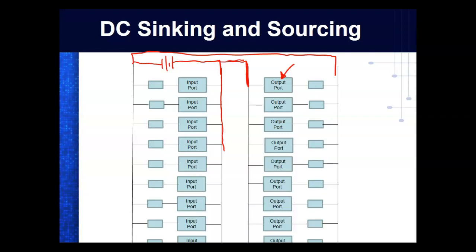So this is technically the way it's wired, and then this right here would be the actual input that's connected there. Some PLCs, this is fixed, and you're not able to configure it for sinking and sourcing. Ours is, but we can't configure all the inputs. Inputs 0 through 3 have their own common, and 5 through 9 have their own common. So we can set 0 through 3 sinking and 5 through 9 sourcing.